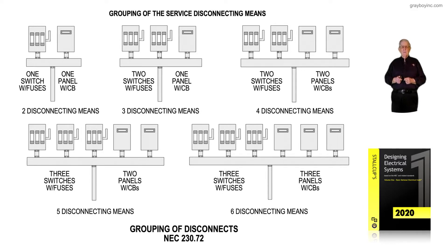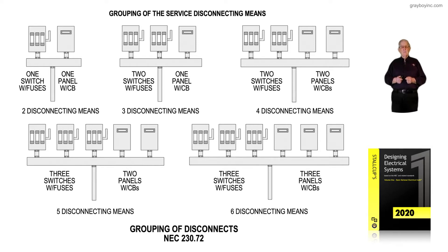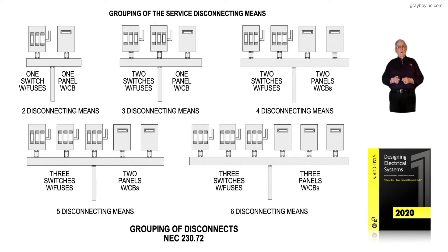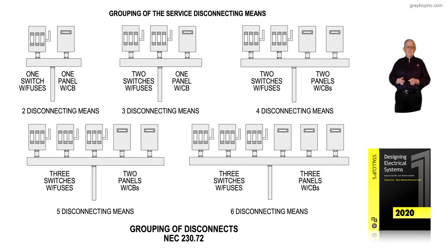This illustration deals with the grouping of disconnects in accordance with 230.72. Looking at the top left-hand side of the illustration, we have one switch and one panel board. Or we could have had two panel boards with a main in each one, or two switches with fuses — it depends on how you're arranging your service to supply the building.